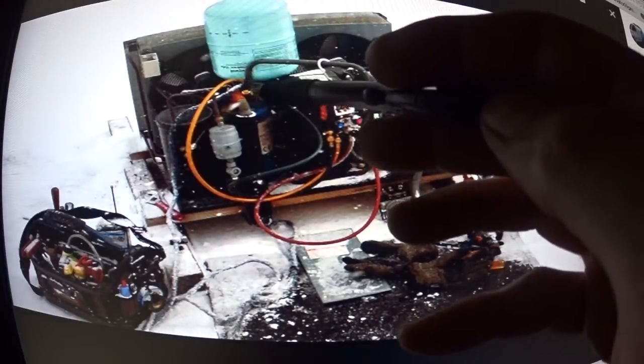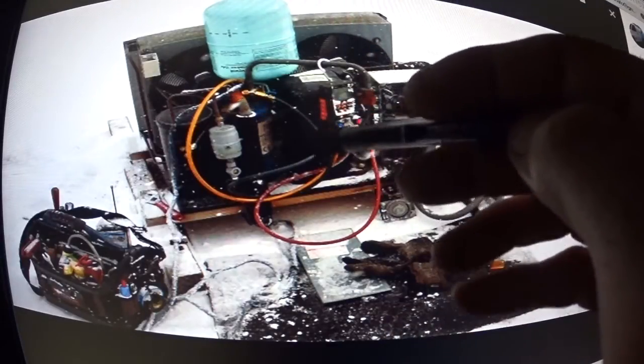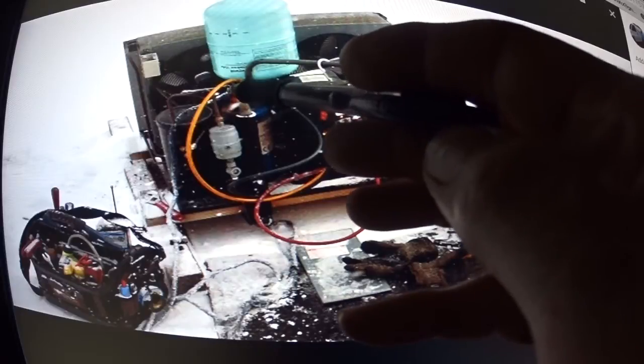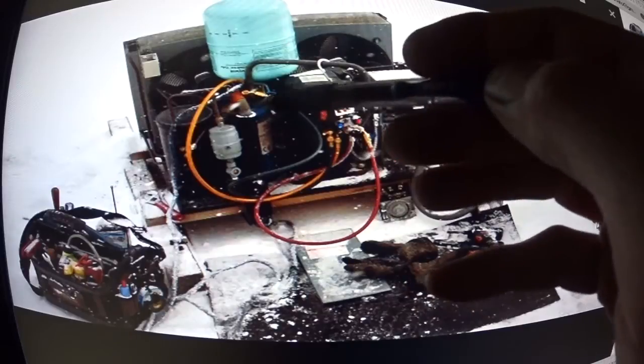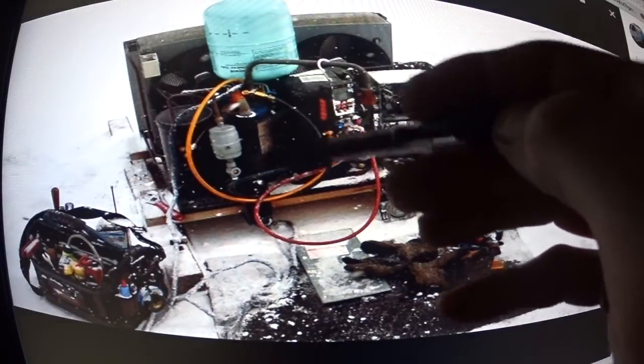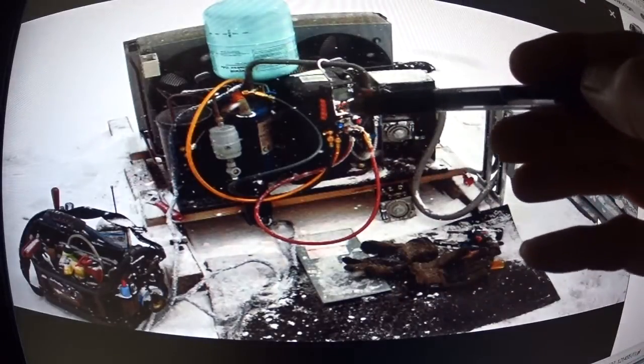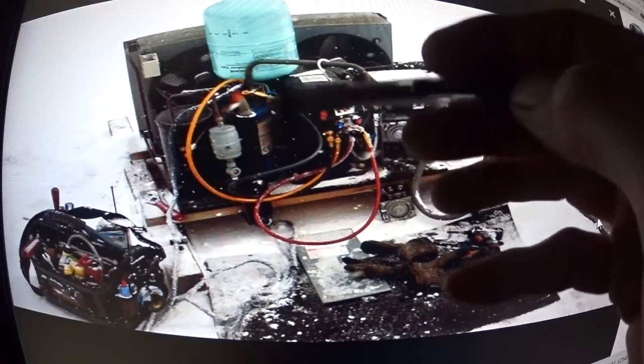The liquid was going in through my blue hose into the suction line, going in before the suction accumulator. The suction gas comes up here and goes into the top of the suction accumulator. It's a tank — if there's any liquid coming back, the liquid falls to the bottom of the tank and gas is taken off the top into the compressor. It protects the compressor from slugging — it's a very good item.